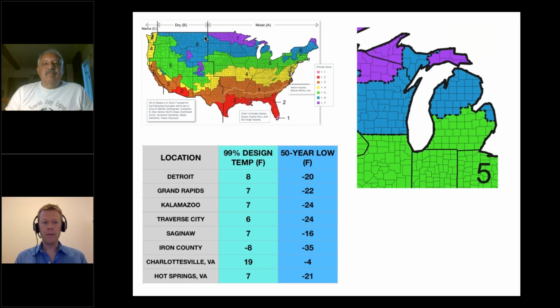So let's talk about climate briefly. Michigan is one of the very few states that's not mountainous but has 3 different climate zones: 5, 6, and 7. Most of the population in Michigan is in climate zone 5. Your design temperatures, the 99% winter design temperature, mean that in an average year 99% of the hours of the year are going to be warmer than this temperature. For most of the state, that's in the high single digits.